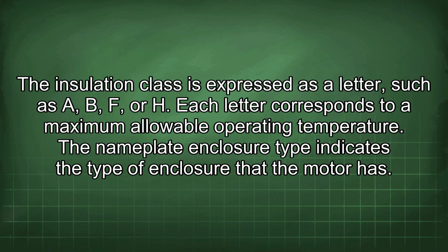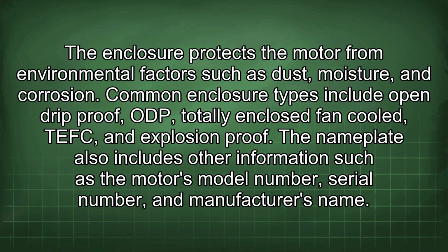The nameplate enclosure type indicates the type of enclosure that the motor has. The enclosure protects the motor from environmental factors such as dust, moisture, and corrosion. Common enclosure types include open drip proof, ODP, totally enclosed fan-cooled, TEFC, and explosion proof.